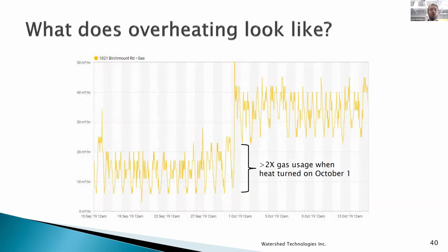So at Watershed, we're really keen on monitoring energy usage on an hourly basis. So here's an example where you can see hourly gas consumption plotted from a typical building from September 15th to October 15th. So you can see when we turn on the space heating system October 1st, we see that gas consumption more than double. And this is a classic sign of overheating because the heating load when we've gone from September 29th to October 2nd, for example, is not increased by double, right? The outdoor temperatures haven't gone down that much, but we see this huge overhead in gas consumption. So that's really costing you a lot and is really what's resulting in that overheating.